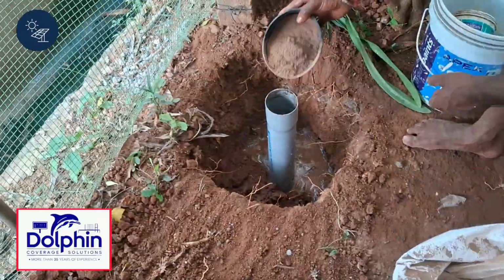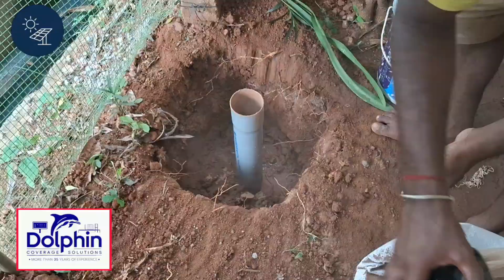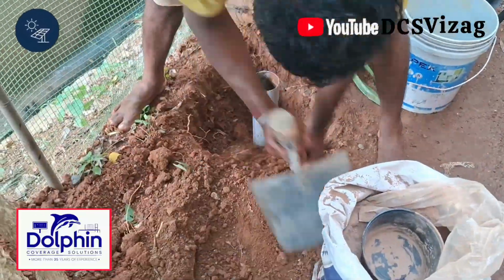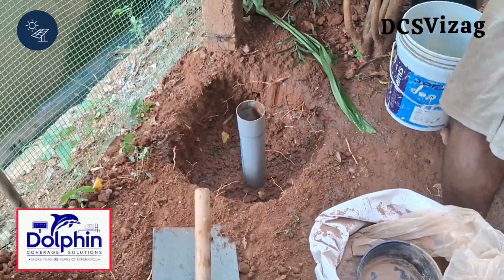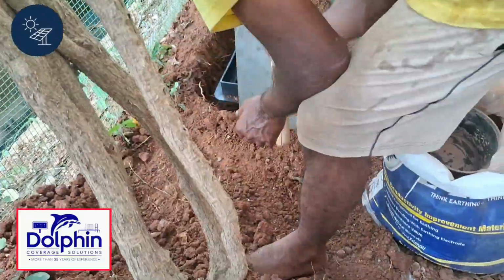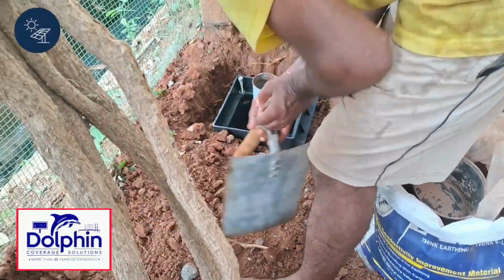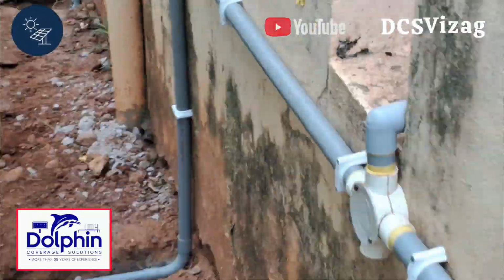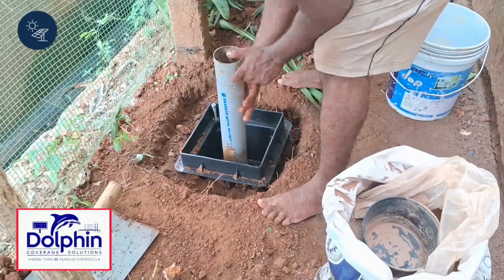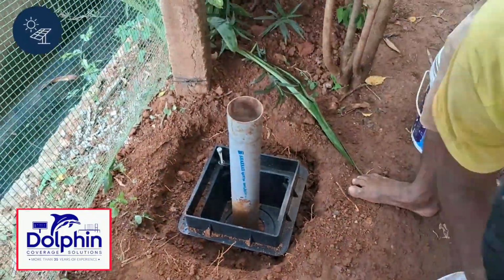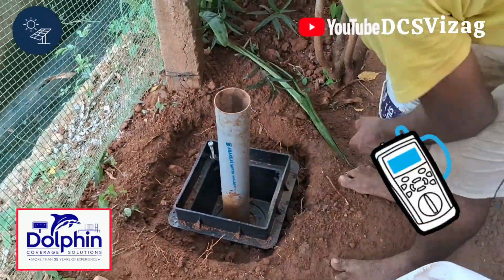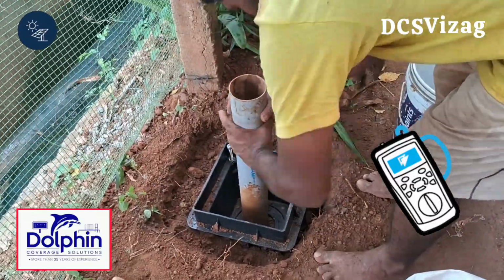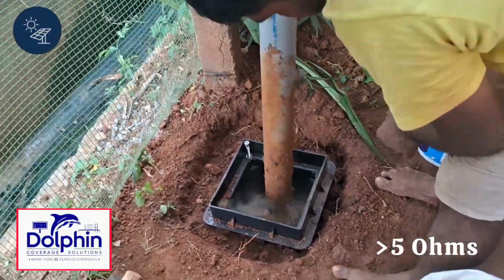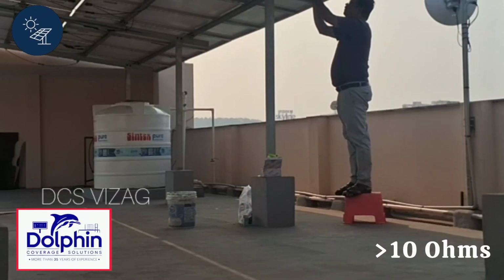Use anti-corrosion materials for all connections, lugs, clamps, and connectors. Ensure proper tightness to prevent loose connections and corrosion. Crimp the cables properly. Ensure earthing cables are routed safely, protected from mechanical damage and environmental exposure. After installation, it's crucial to measure the earth resistance using an earth resistance tester. The measured value must be within the acceptable limits, typically less than 5 ohms for equipment and less than 10 ohms for the lightning arrestor.